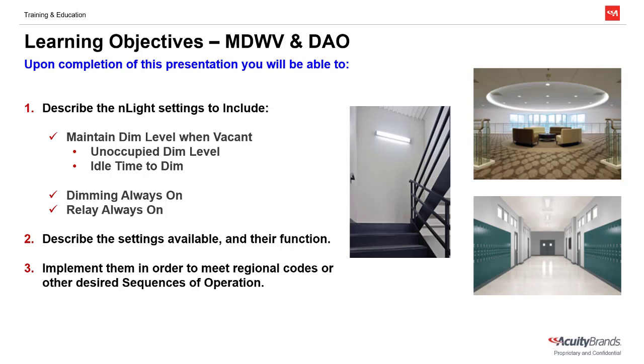NLIGHT output devices like power packs and NLIGHT enabled fixtures contain the setting Maintain Dim Level When Vacant. Furthermore, we may also wish to not allow the occupants of a space to switch lights off. The settings Dimming Always On and Relay Always On can be used to accomplish this behavior.